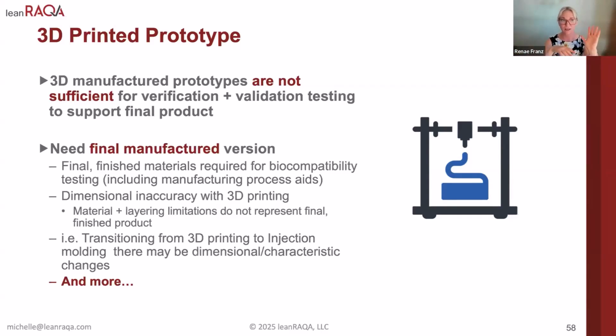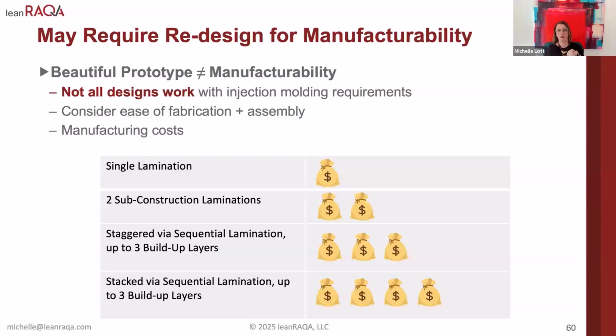The other issue when you transfer a design from a 3D printed to an injection molded part is that there tend to be dimensional inaccuracies. 3D printed prototyping works by layering one dimension over another, while injection molding is basically flowing plastic through almost like a port and into a mold that you've created. So I've seen a lot of times where we've had beautiful 3D printed prototypes, but we go to manufacture and injection molding and the walls are just way too thin. So a lot of times you do have to think about design for manufacturability as you move from prototyping into your final injection molded plastic part. And you also have to be prepared that the FDA is going to ask how the unit under test compares to the unit you intend to commercialize.